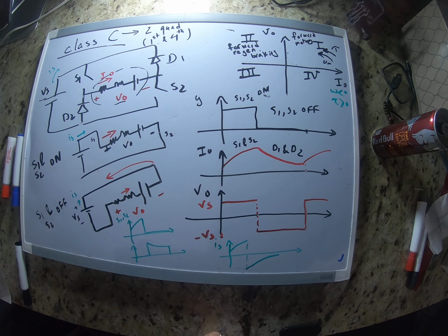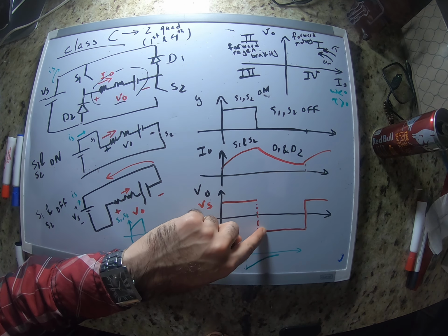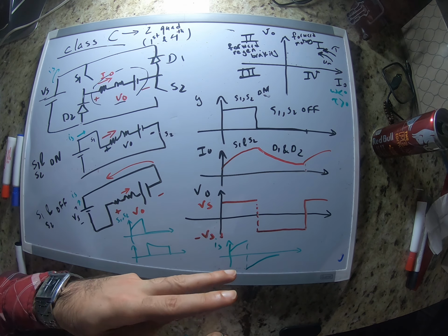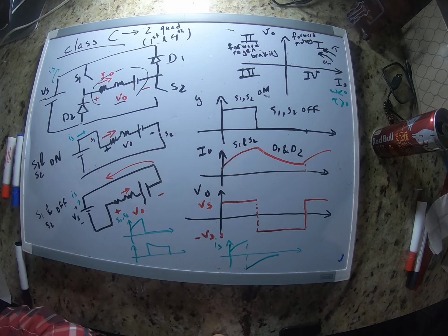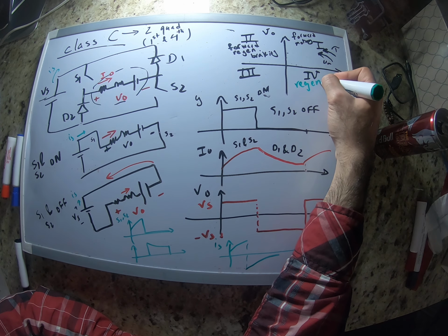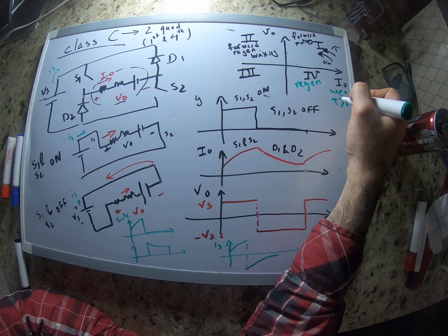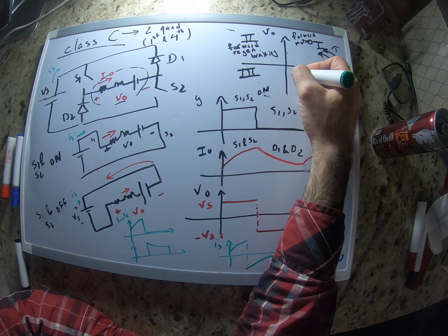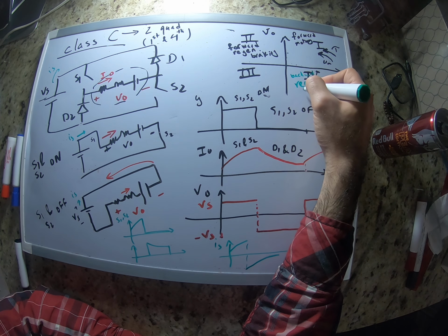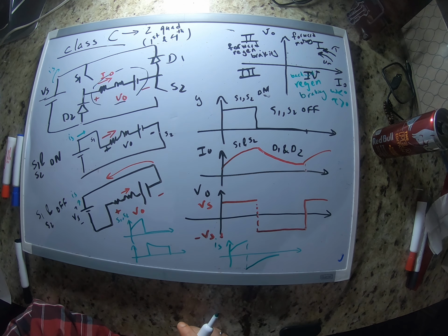Okay, again, you can see that the polarity of the voltage and current are opposite, right? So it means that we are having negative power. It means that we are in the generation mode. So this is regenerative, right? But it's regenerative in the opposite direction. So it means backward regenerative braking. Okay.